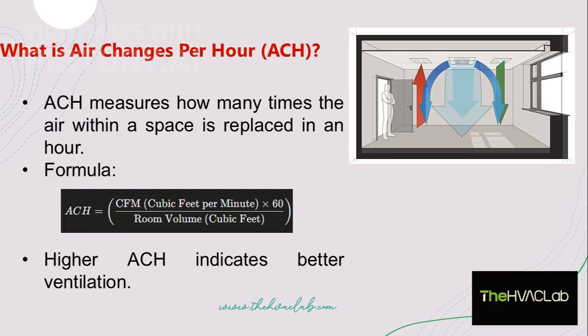ACH measures how many times the air within a space is replaced in an hour. The formula to calculate ACH is the airflow rate in cubic feet per minute multiplied by 60, divided by the room volume in cubic feet.